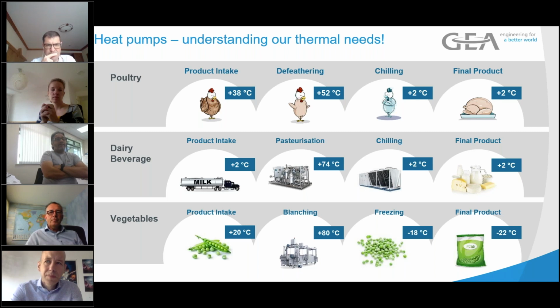So the top line, you can see the poultry guys. You know, the chicken goes in feeling happy and warm at 38 degrees. The first thing they do is they defeather and eviscerate it, where they use heat to open up the pores and take the feathers off. And then the bird gets chilled, it may get portioned, it may get frozen, but it leaves cold. They use a boiler for heating it up, and they use a refrigeration plant for cooling it down.